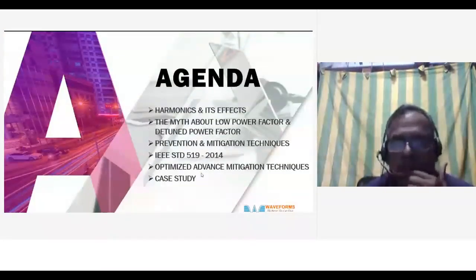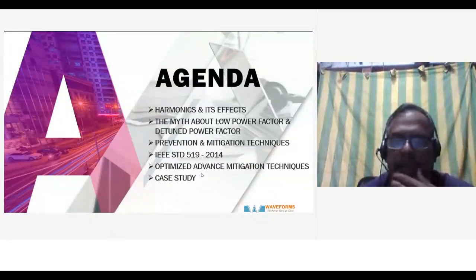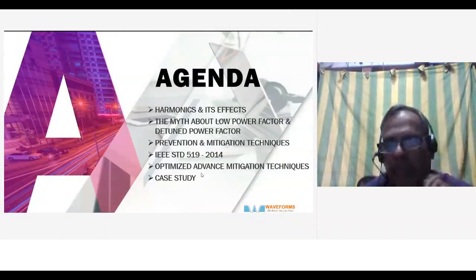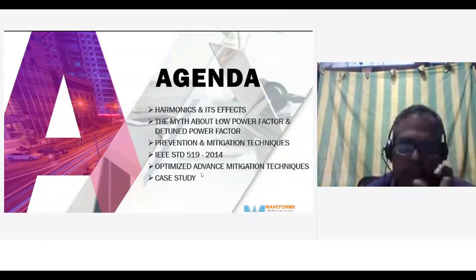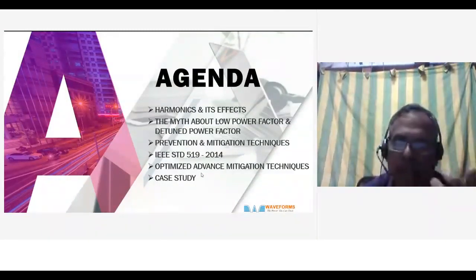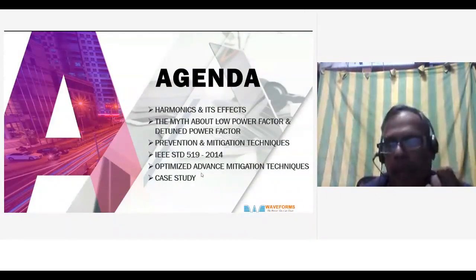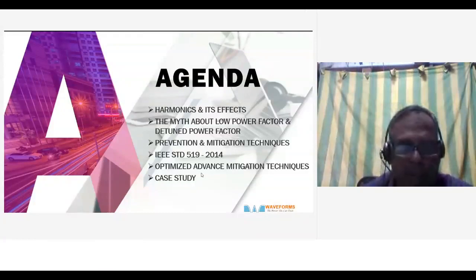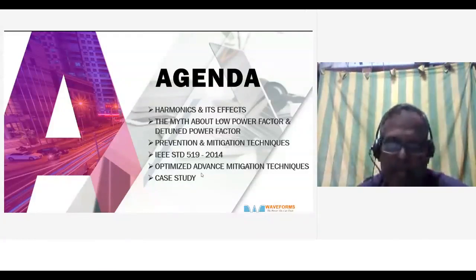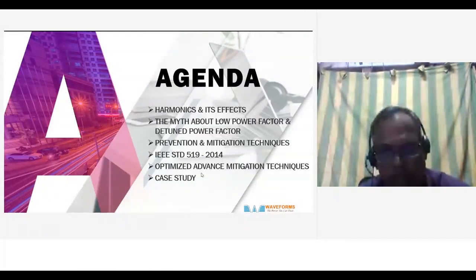So our agenda is harmonics, its effects, the myth about power factor, because that's a very critical subject. In a new environment, due to harmonics and pollution, power factor will become difficult to maintain. Then prevention and mitigation techniques, and support for the IEEE standard 519/2014, which is the latest standard for harmonic mitigation. And then the advanced mitigation techniques, and then a few case studies.